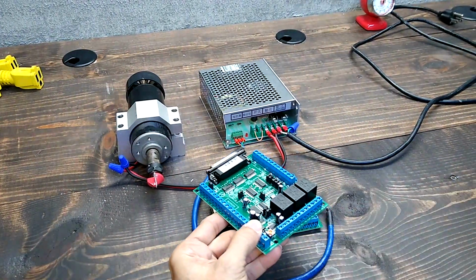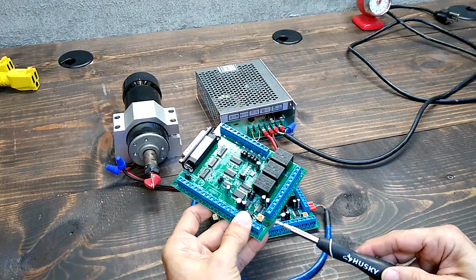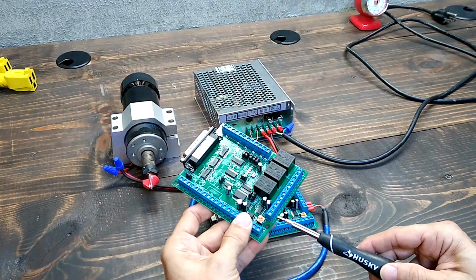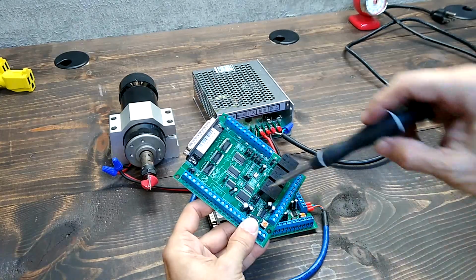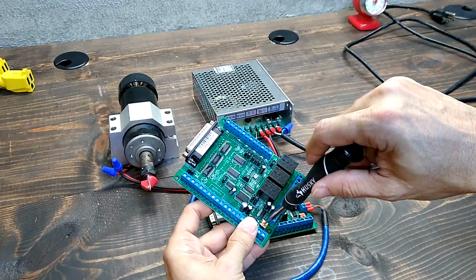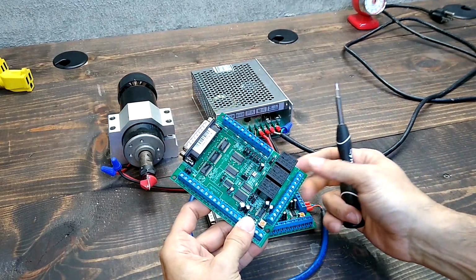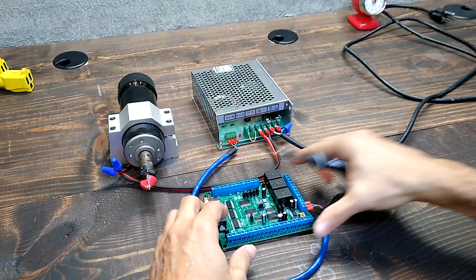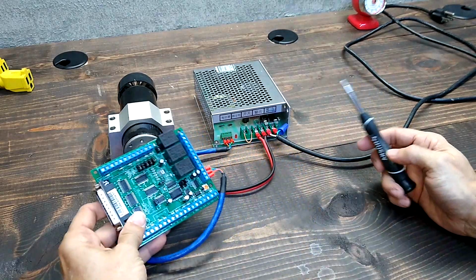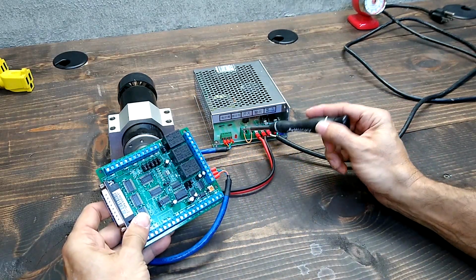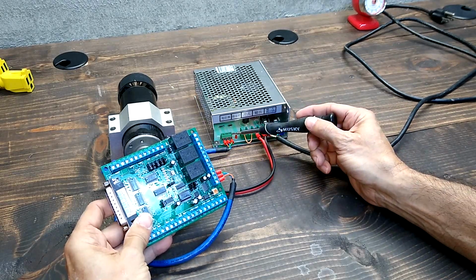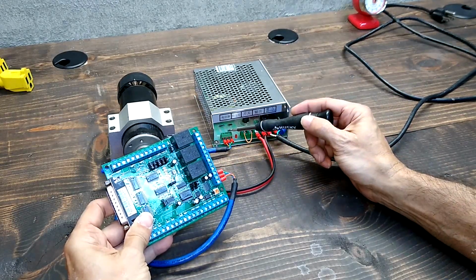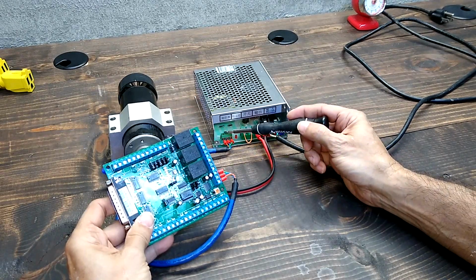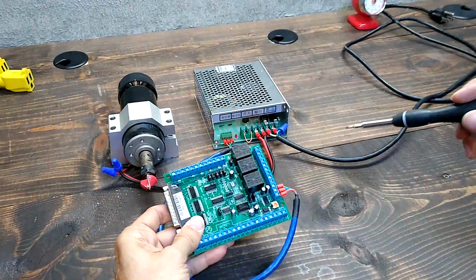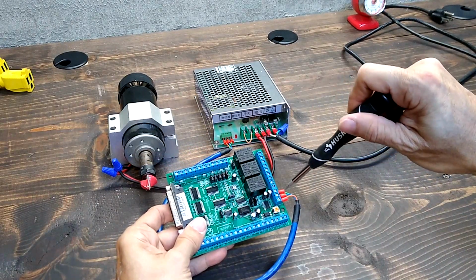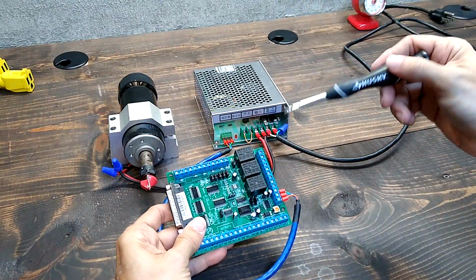To connect the spindle speed control, we will be using 12 volts, voltage in terminal, 0 to 10 terminal, and ground terminal. We have a potentiometer to adjust the 0 to 10 voltage. Now we connect ground, 0 to 10 volts, and in this case 5 volts, which we will need to adjust the potentiometer, setting it to max and then tune it down.